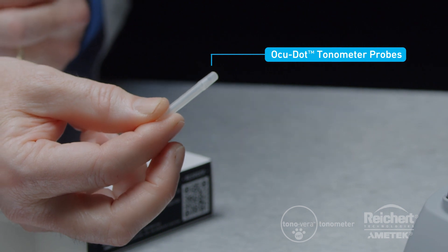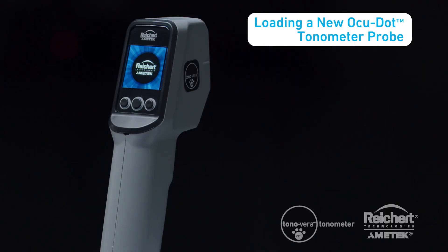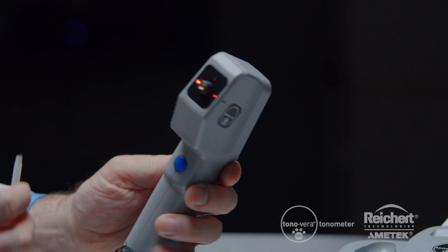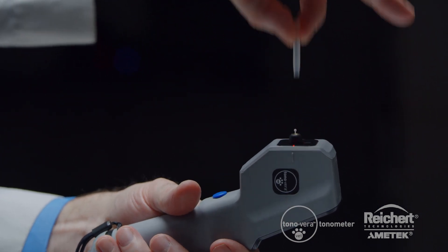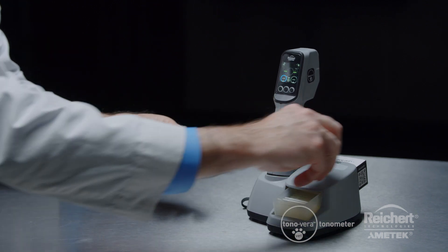Ocu-Dot tonometer probes are single-use and sanitized to prevent the risk of cross-contamination. Loading a new Ocu-Dot probe is easy. Power on the Tono-Vera Vet — the screen will then prompt you to load a new Ocu-Dot probe. Remove the cap from the Ocu-Dot probe tube and insert the end of the tube into the chamber. Rotate the unit up so that the Ocu-Dot probe slides into place. Conveniently store the probe tube in the base recess while you're taking a measurement.